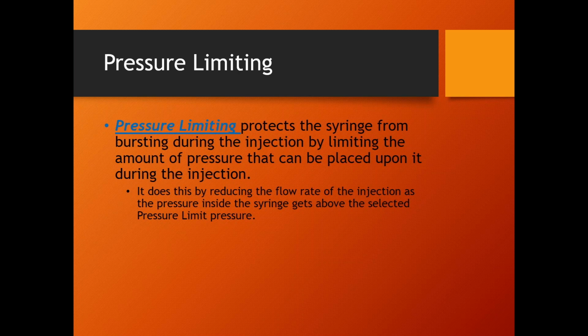Now, for angio or for CT and contrast injectors, if for whatever reason during our injection the system hits its pressure limit, say we're doing a CT injection and it hits 300 psi, right? It does not stop the injection. All right, we don't want to stop the injection in the middle of this procedure.